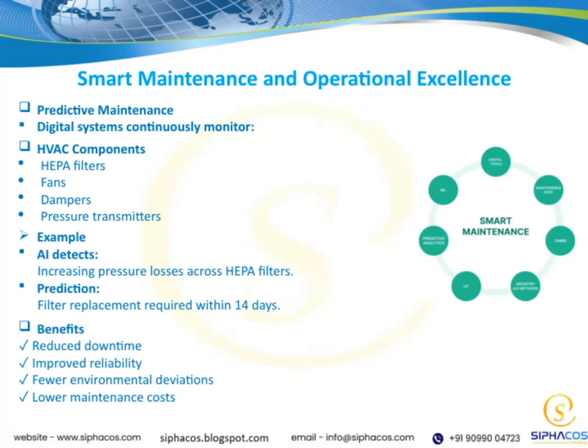Smart maintenance is all about working smarter, not harder. With predictive maintenance, digital systems keep a constant eye on key components, like HVAC parts, HEPA filters, fans, dampers, and pressure transmitters. For example, AI can spot rising pressure losses in HEPA filters and predict when a replacement is needed, say within 2 weeks. This approach cuts downtime, boosts reliability, minimizes environmental hiccups, and lowers maintenance costs. It's a clear win for operational excellence.